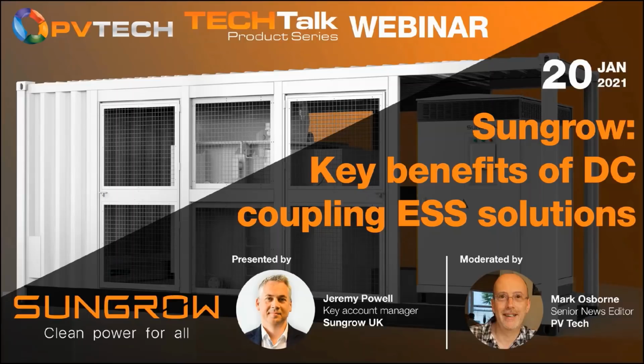You mentioned the discharge side - can the batteries be discharged during PV generation with the PV curtailed to zero export? If there's zero export to the grid, can the PV still charge and discharge the battery? It can charge the battery, but if you're discharging, you wouldn't be able to, because the system's curtailed - zero export, there's nowhere for the energy to go. But in one non-standard scenario, if there is PV being generated, you can store that directly into the batteries.